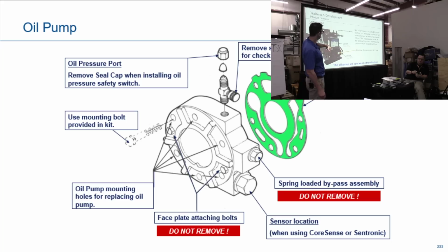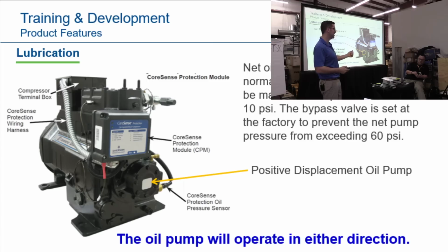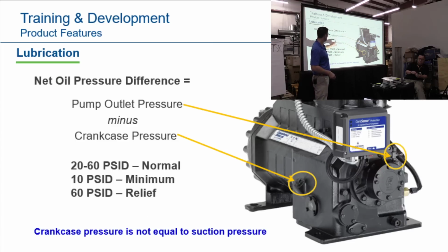So CoreSense, this is our oil style CoreSense. If your oil pressure gets down below 10 psi differential, it'll shut the compressor off to protect, say there's no oil. Okay, so that's the protection. So you've got to figure out why. Is it a dirty screen? It's pump outlet pressure minus crankcase pressure. So as you see, you put a gauge on here, you put a gauge on here, and then you subtract the two to get your net oil pressure. Okay? Crankcase pressure is not equal to suction pressure. We talked about that already.